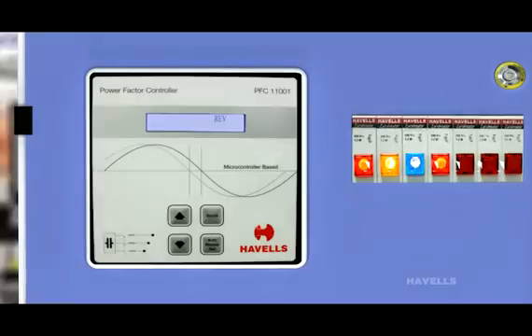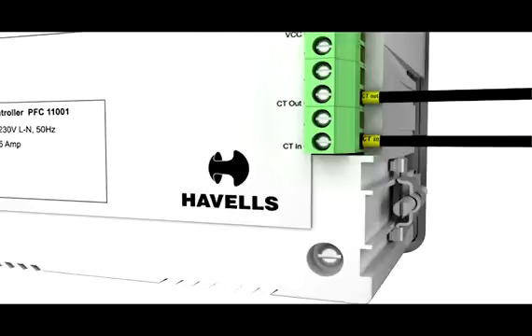Switch on load and check display. If REV appears on top right-hand side in the display, then interchange the CT in and CT out wires. Otherwise, relay will not function in reverse condition.